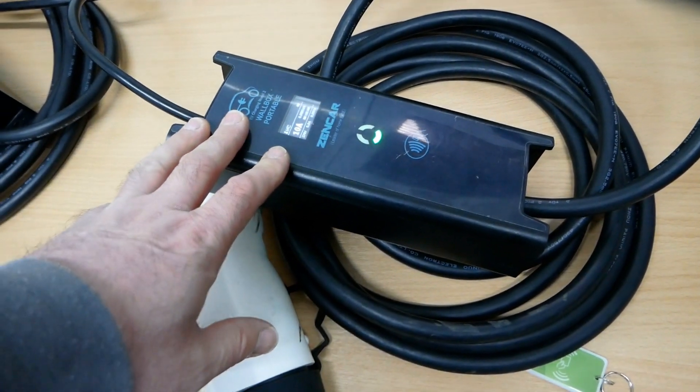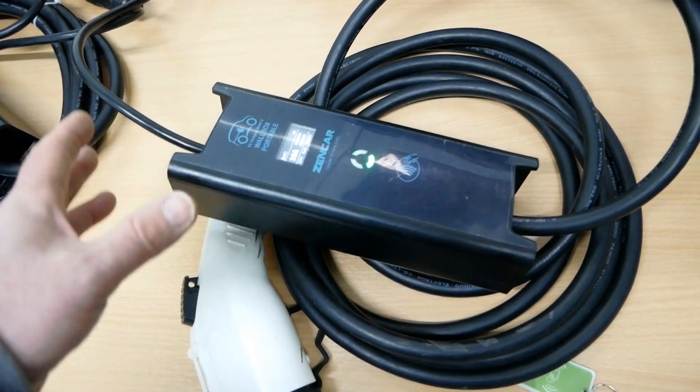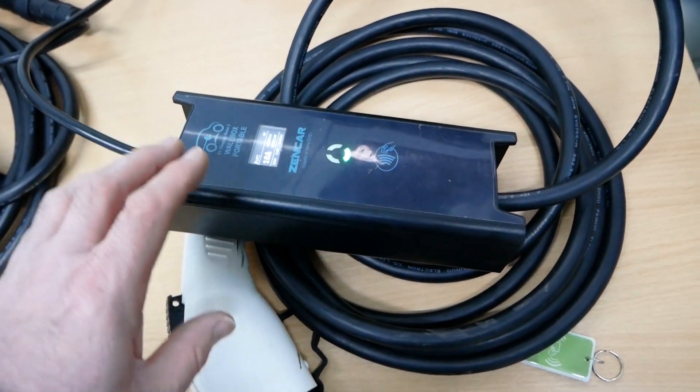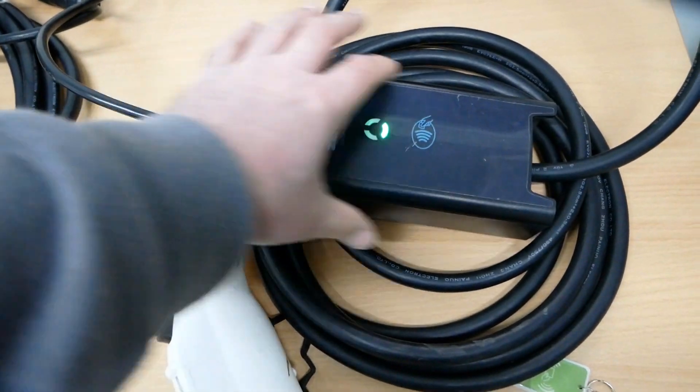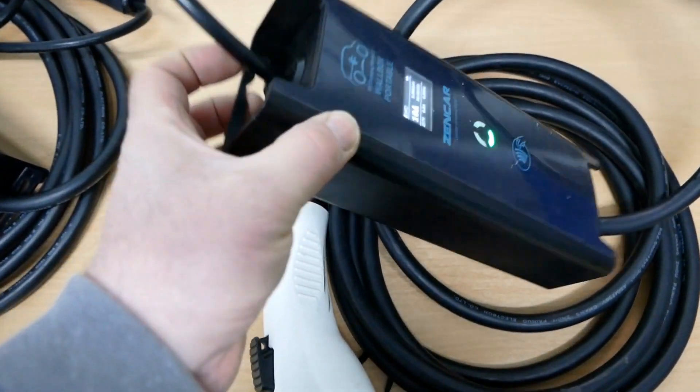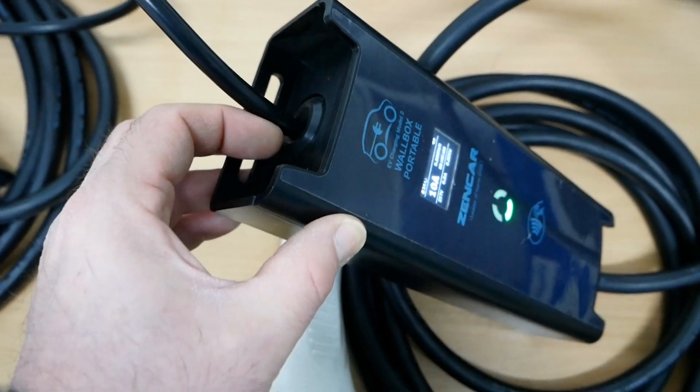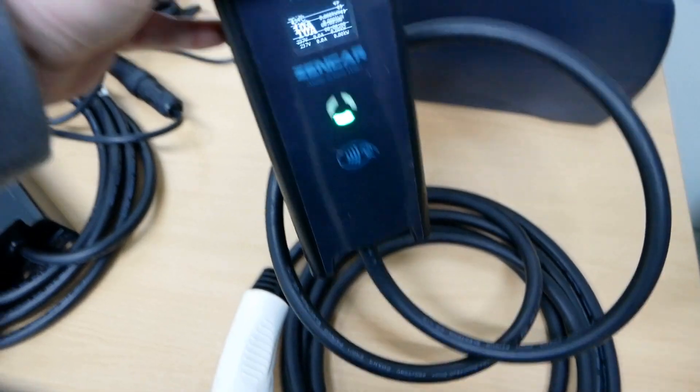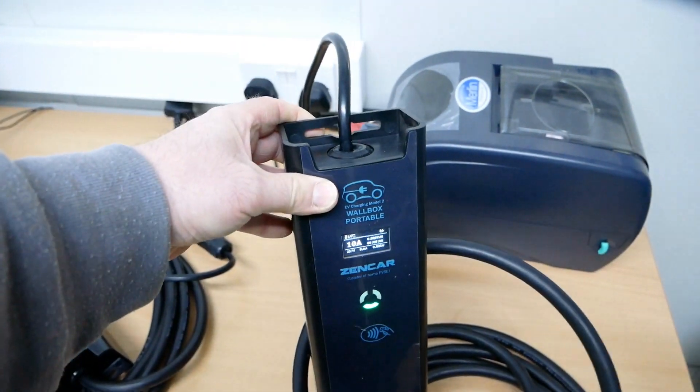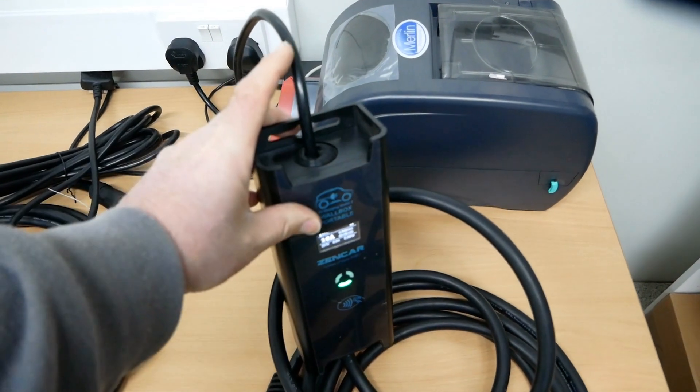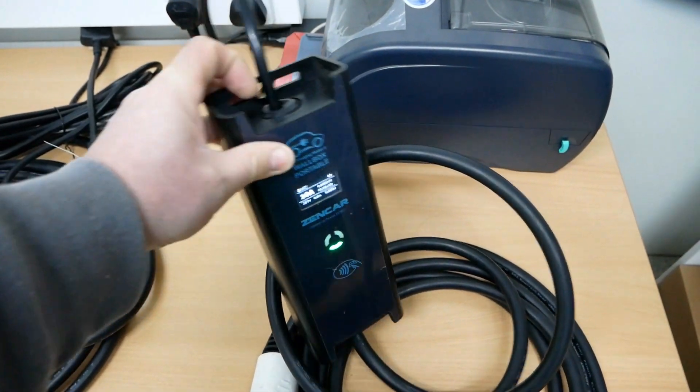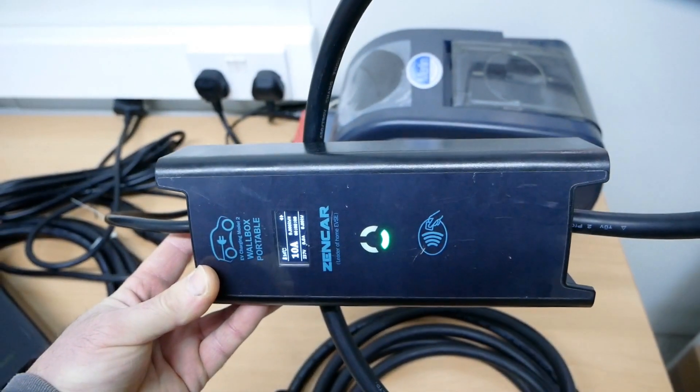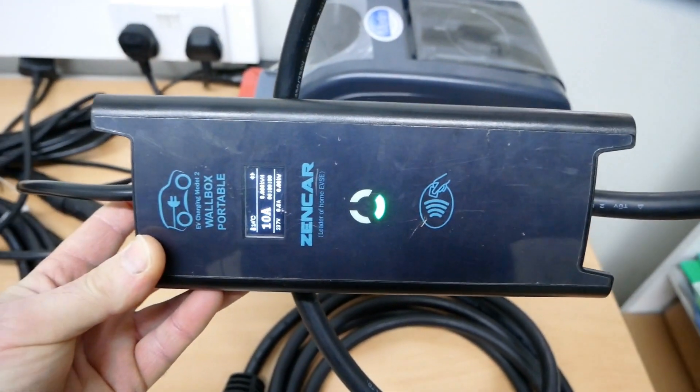The other thing you have to be wary with these is they're not fully waterproof, and that's the same with all portable chargers. You will see there'll be many brands of chargers with this style of packaging or carcass, and the grommets at the end—they aren't 100% waterproof. So a lot of times you might end up hanging them that way off a socket high up a wall, and that's where you got to be careful because water might run down the cable and it will get in through that grommet. You're better off having them that way so there's less chance of water getting in either end.